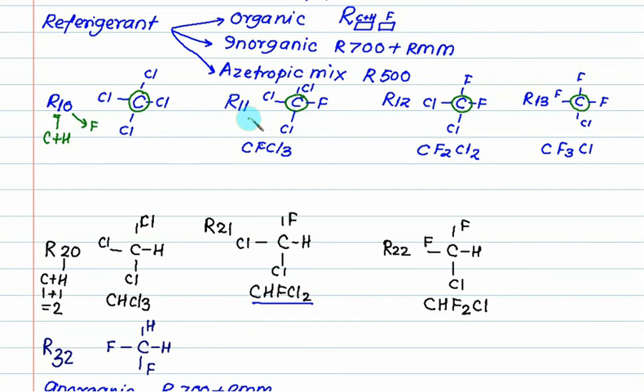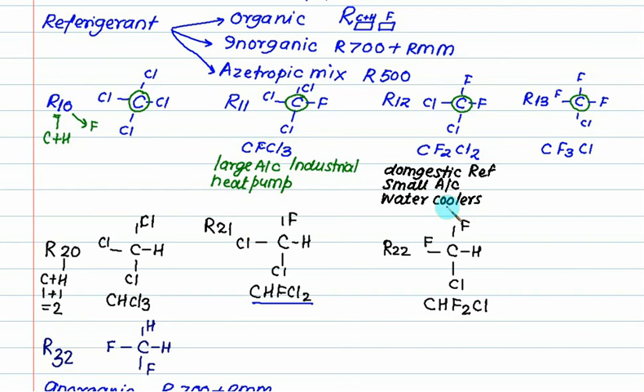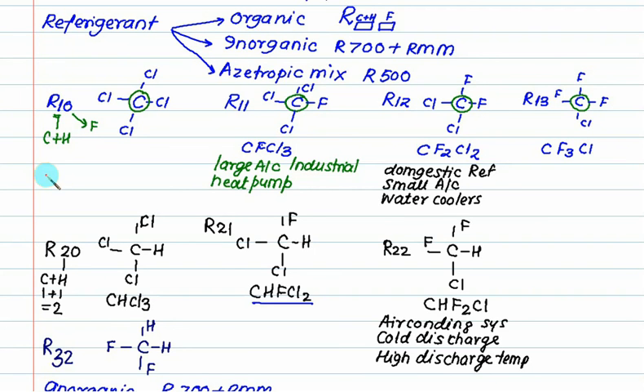R11 is used for large air conditioners. R12 is normally used for domestic refrigerators and water coolers. R12 is cheaper compared to R11, that's why it's used in domestic and small AC. All these refrigerants contain chlorine, and chlorine is responsible for ozone depletion.